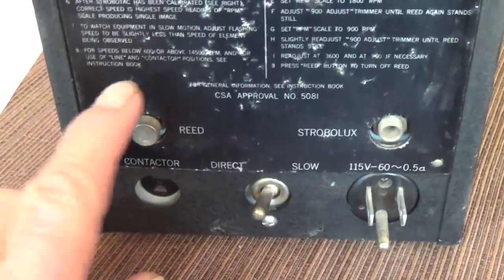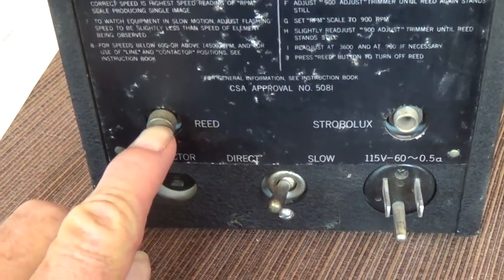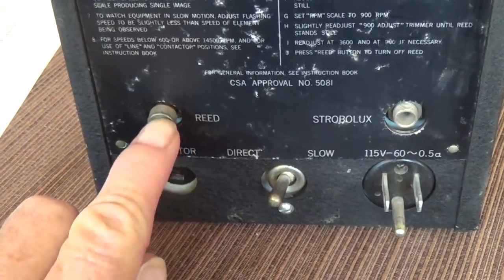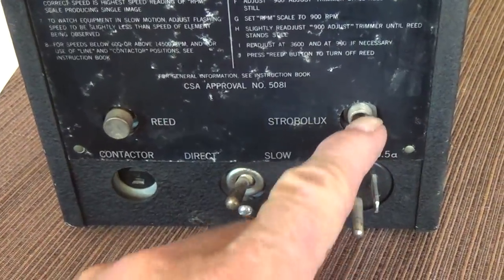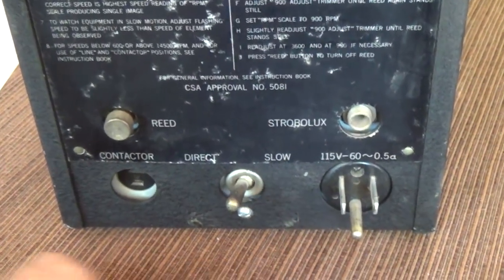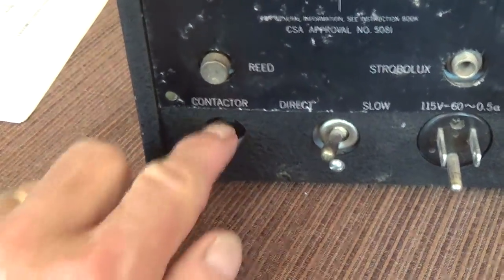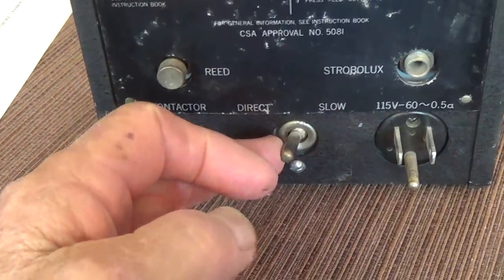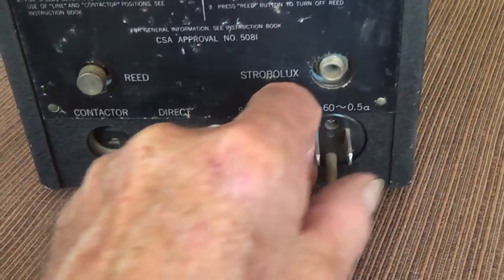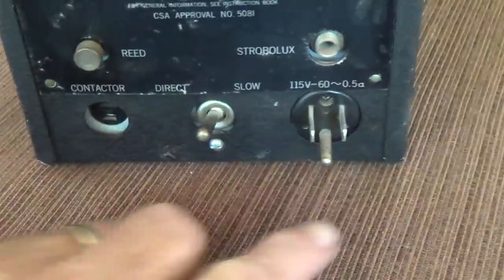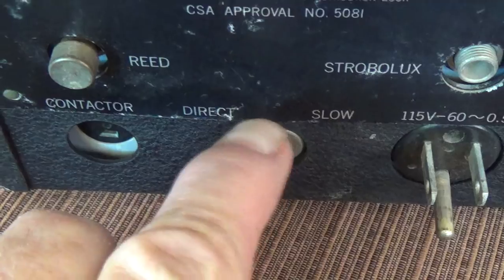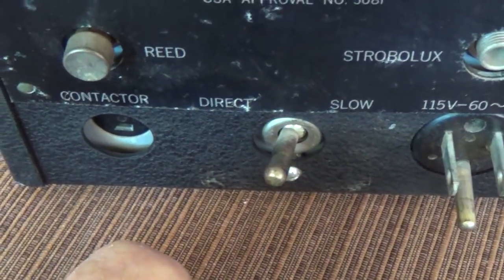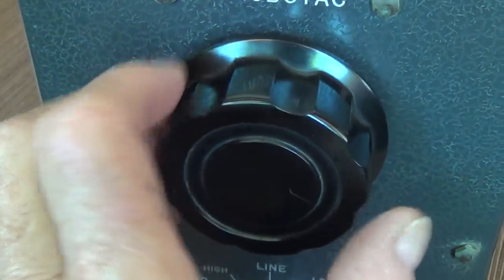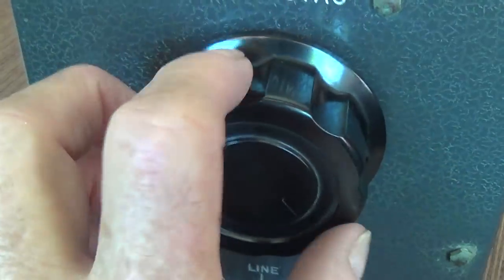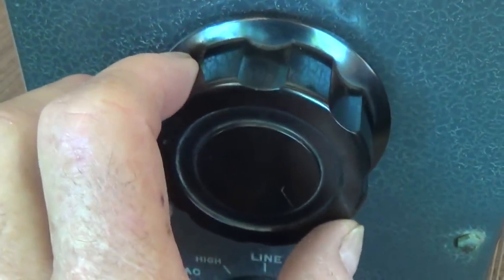Down below here we turn on that reed, remember up at the front under this strobe tube, so that we can calibrate it. This turns the reed on and off. This is the external feed for the larger strobe light if we want to use it. This is for the external trigger. We have something called direct and slow toggling here, which I'll explain in just a second. And over here, of course, is the male part where we plug in the female part of our cord, our power cord. 3-wire too, you notice, grounded, which is nice. When the toggle is in direct position, you can use the large speed control knob here to vary the strobe rate from 60 all the way up to 14,400 flashes per minute.